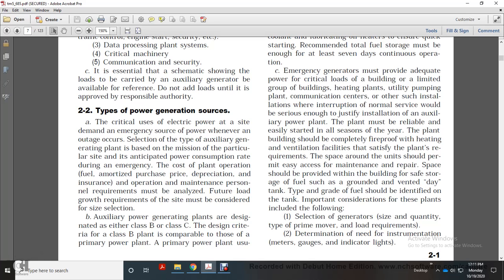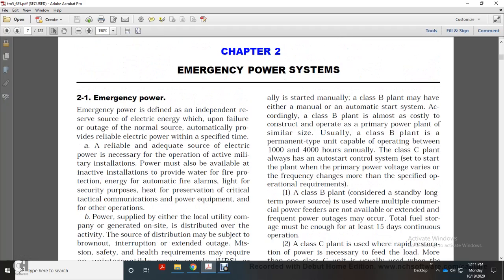Auxiliary power generator plants are designated either as Class B or Class C. The designation criteria for Class B are comparable to those of a primary power plant, which is usually started manually. Class B power plants may have either manual or automatic start systems. Class B plants are costly to operate and control, similar to a primary power plant of similar size.